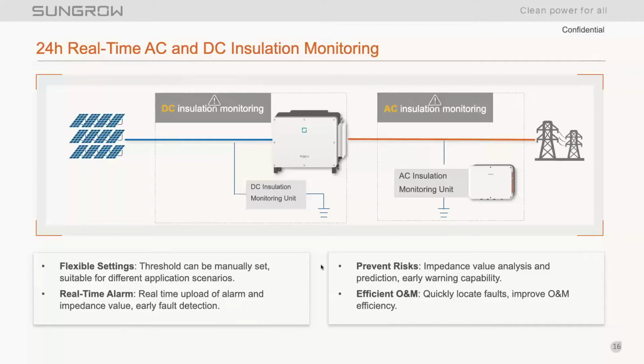So if you have a site where you're starting to kind of see some insulation resistance issues, you can lower that value as a troubleshooting mechanism, and it'll really help you narrow down and find out exactly what portion of the array you're experiencing those insulation resistance issues in, so that technicians can get pointed in the right direction, as opposed to finding a needle in a haystack in a full array.